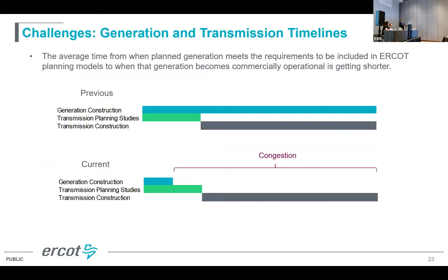So in this slide, I captured the key challenge between generation and transmission timelines. Traditionally, generation construction took 3 to 4 years through the interconnection process, so you would have time to plan the transmission system. You do the studies, put the projects in place, and get those projects on time. The current situation is that generation IBRs are connecting in 18 months or even shorter for batteries. That challenges the planning process, which has to evolve. We're still doing the studies, and with supply chain challenges, construction times will take similar time or more. So you have to deal with system congestion until the transmission catches up.